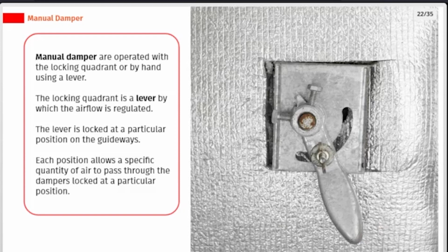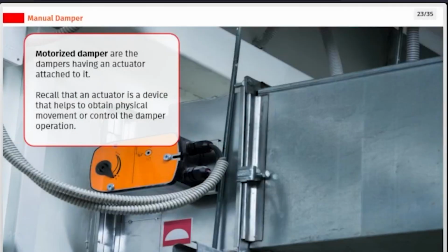Manual dampers are operated with the locking quadrant or by hand using a lever. The locking quadrant is a lever by which the airflow is regulated. The lever is locked at a particular position on the guideways. Each position allows a specific quantity of air to pass through the damper locked at that position. Motorized dampers are dampers having an actuator attached to them. Recall that an actuator is a device that helps to obtain physical movement or control the damper operation.